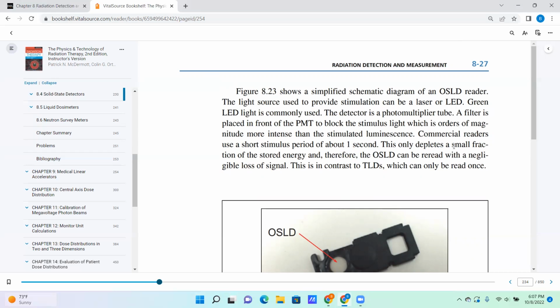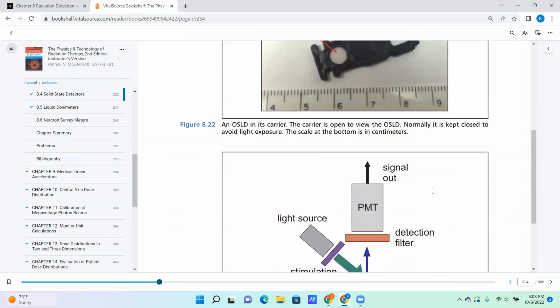The process here is that light is used to provide stimulation, and it can be a laser or LED. Green LED light is commonly used. The detector is a photomultiplier tube. A filter is placed in front of the PMT to block the stimulus light, which is orders of magnitude more intense than what is going to be luminesced. Commercial readers use a short stimulus period of about a second. This only depletes a small fraction of the stored energy, and therefore the OSLD can be reread with a negligible loss of signal, unlike TLDs, which can only be read once.